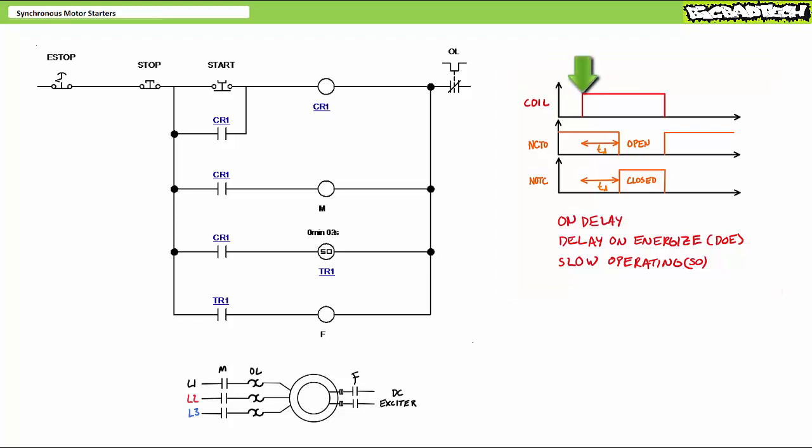When the timer coil energizes, the associated normally closed contact remains closed and the normally open contact remains open. Only after the predetermined delay TD has elapsed does the normally closed contact open and the normally open contact close. When the timer coil de-energizes, the associated contacts immediately return to their deactivated states, i.e., the normally closed contact recloses and the normally open contact reopens.